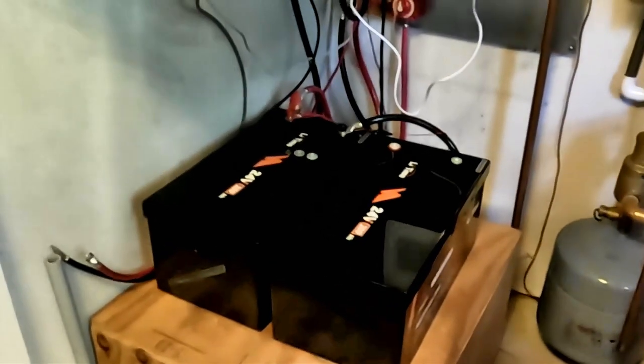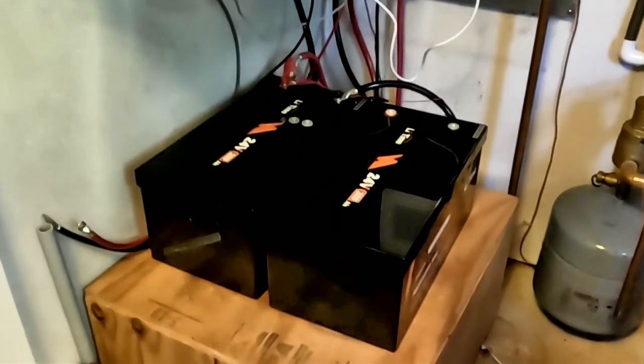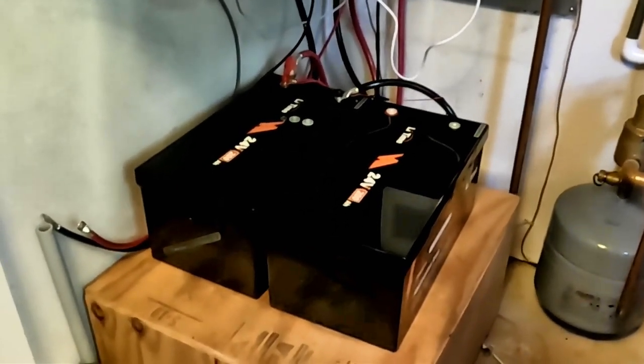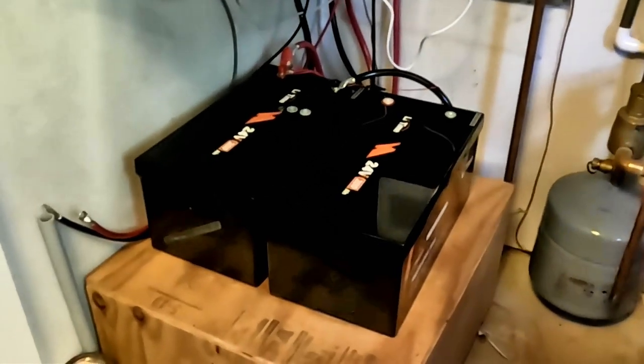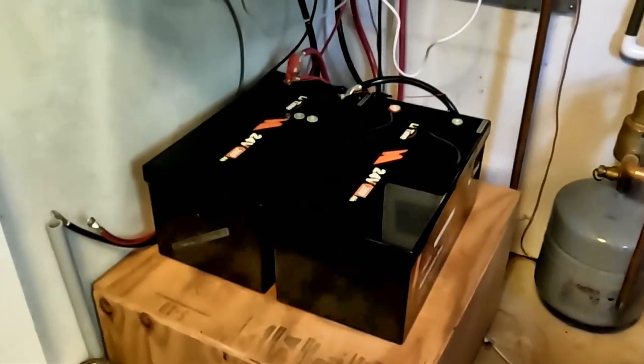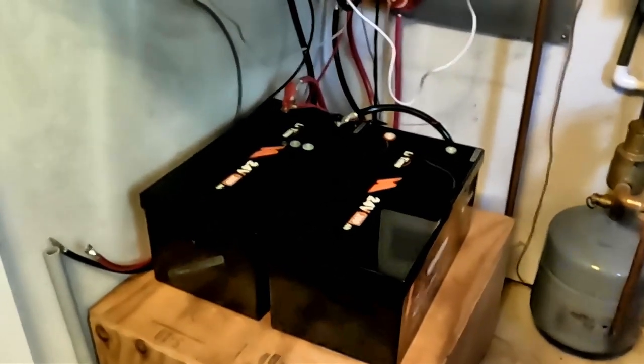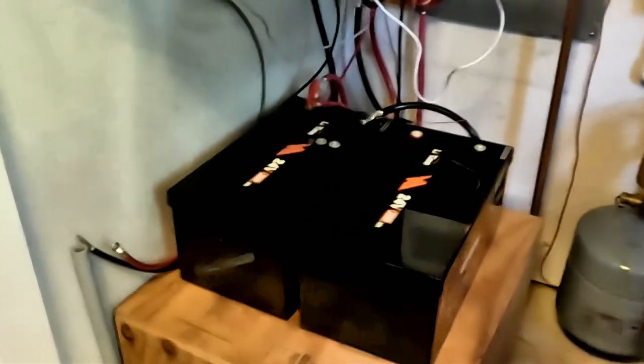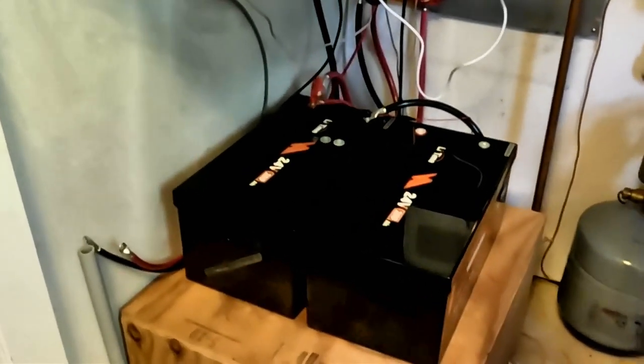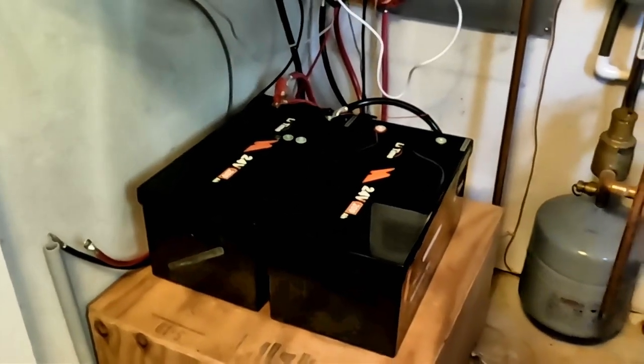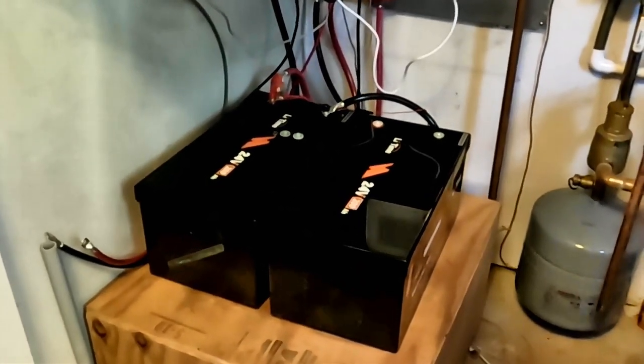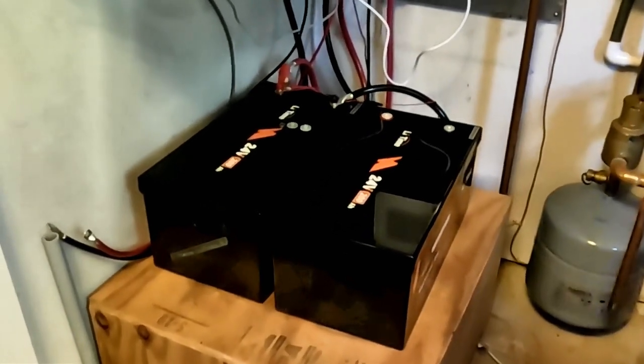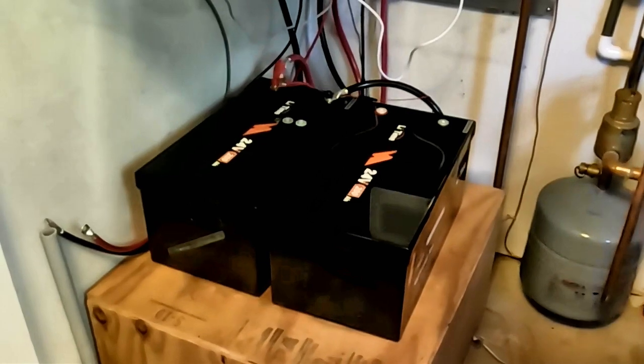I have it set up to a transfer switch and an isolated power panel for the circuits that we run off the battery backup system, so it's safe to do. When it's running off battery backup there is no connection between the inverter and the batteries and the grid, so it doesn't matter what's happening there. The system will continue to run, and even when the power comes back on, until I turn it off.